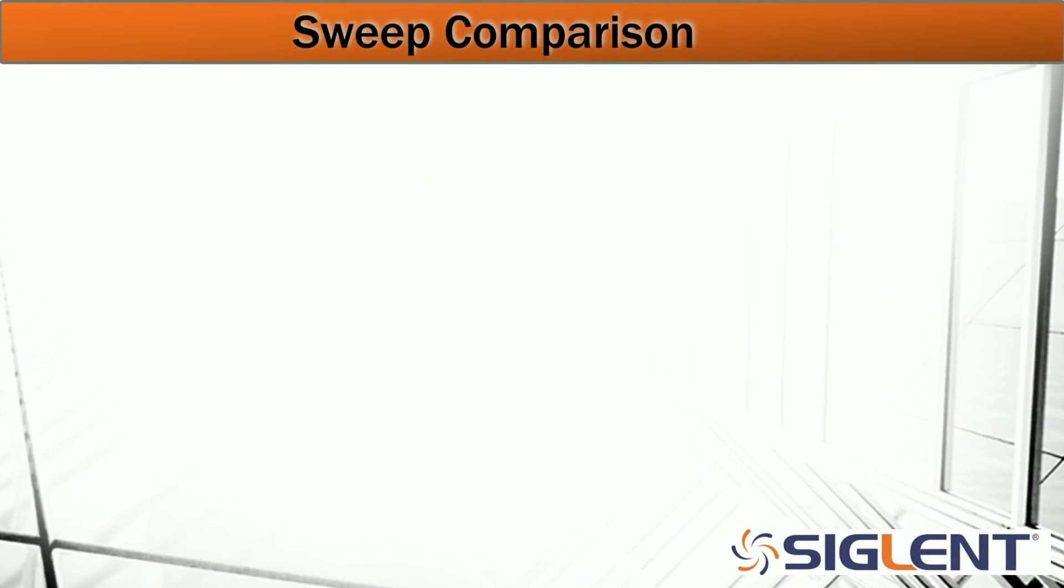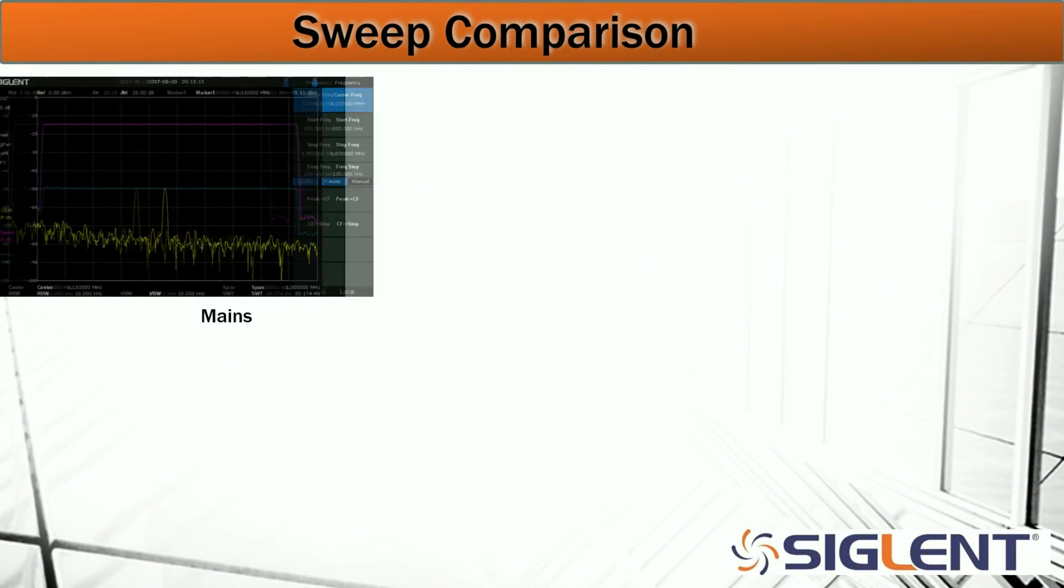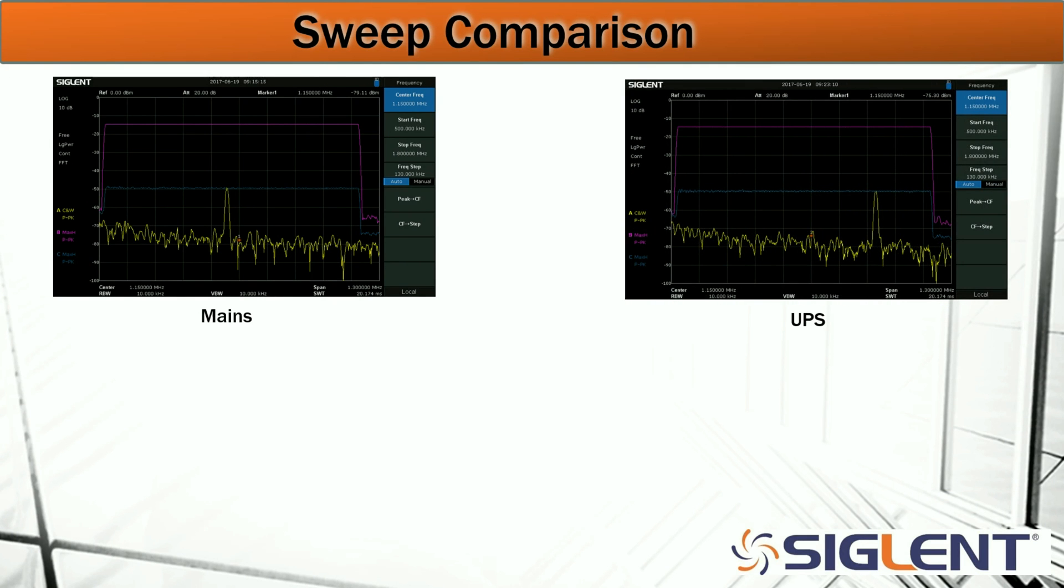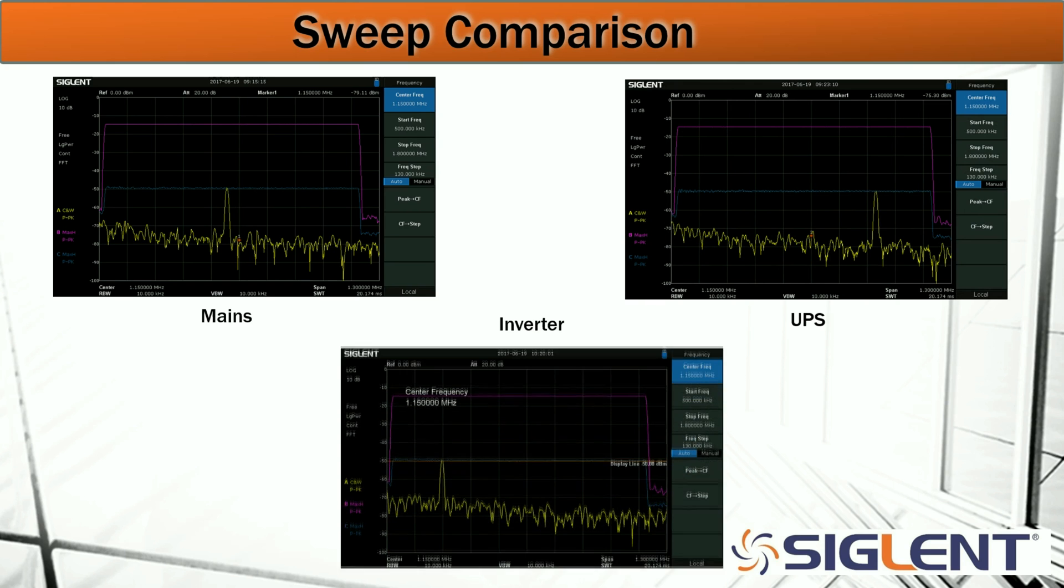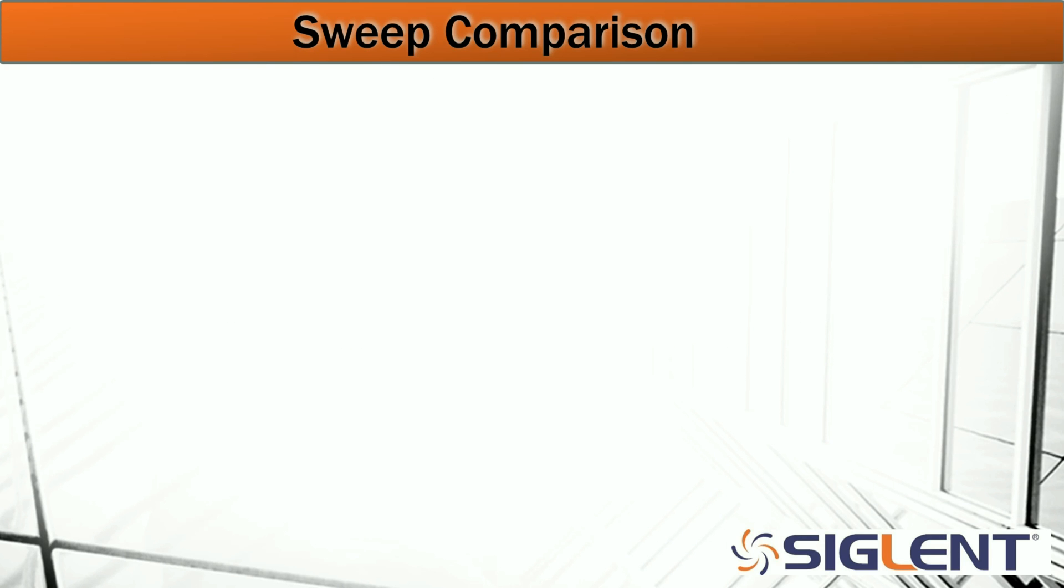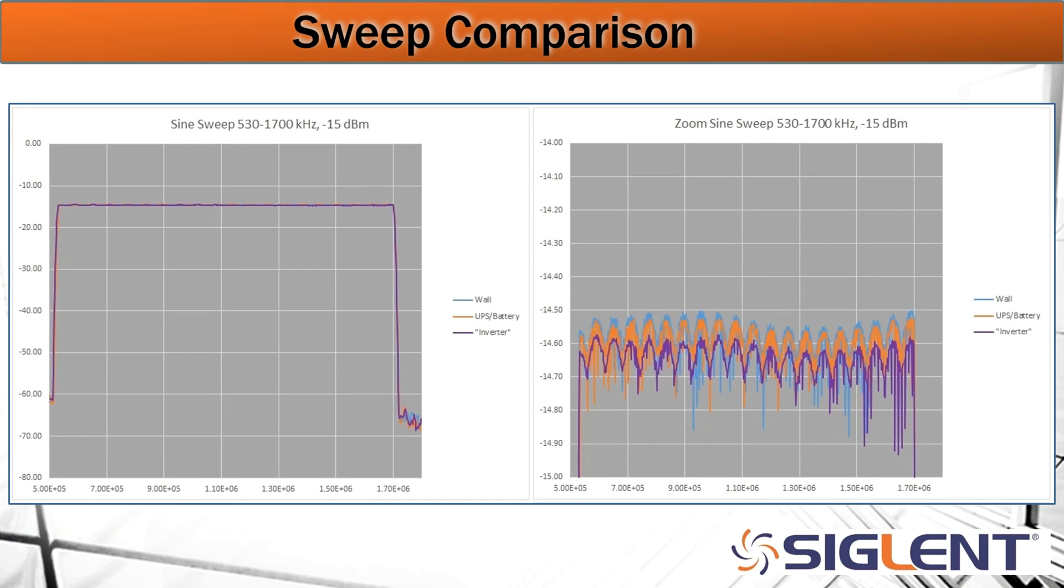We can easily compare all of the data collected from the different power modes using the bitmap images. Here we've got mains of the sweep, the uninterruptible power data, and then also the data collected using the inverter. Again they look quite similar, but we can also collect the raw CSV file data for each of the individual sweeps and then compare them or overlay them in a spreadsheet program.